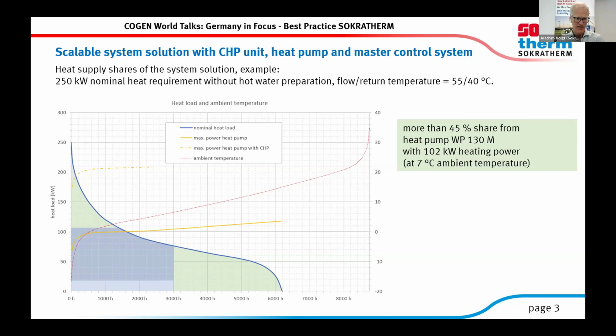Stefan also mentioned the GEG, the building law for heating buildings, and it states that the heat pump has to be big like this for a hybrid system consisting of heat pump and gas boiler. But in the rest of Europe, I'm sure that the heat pump can also be designed a little smaller. The share will be quite the same.